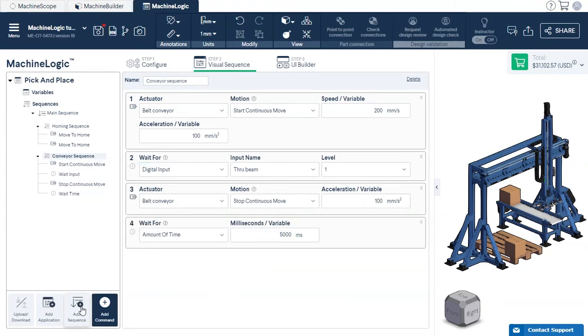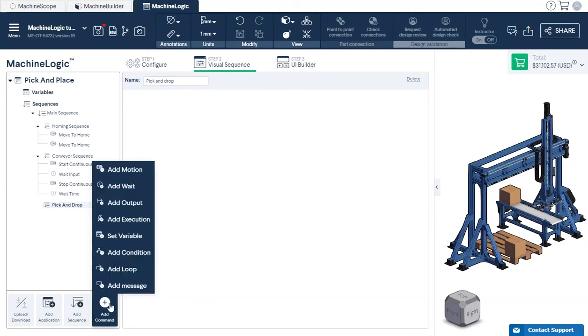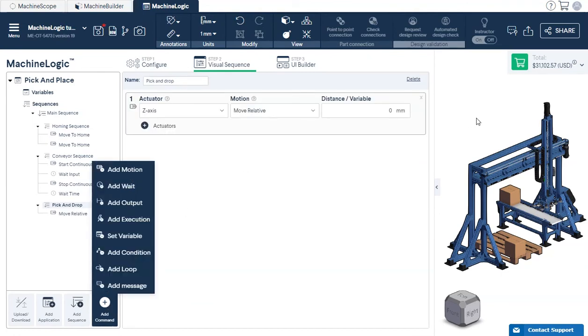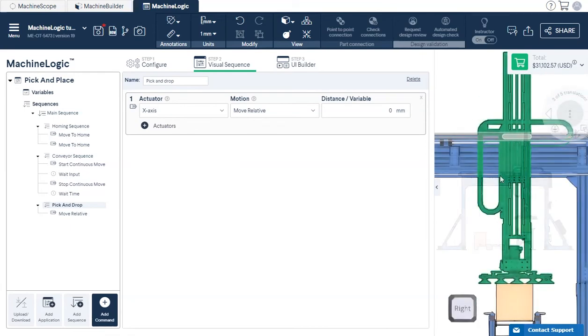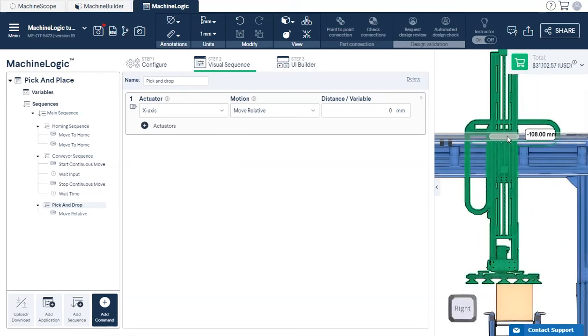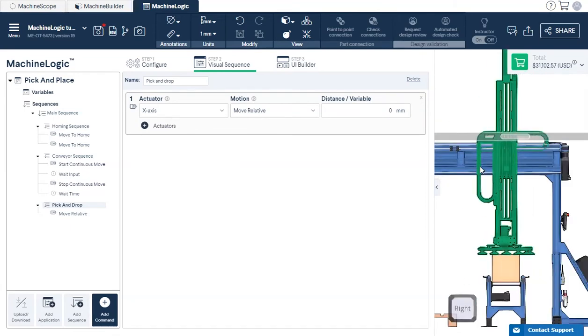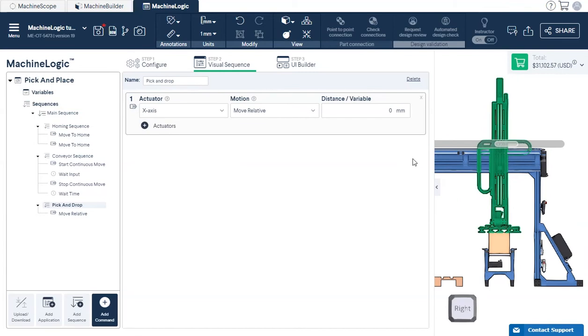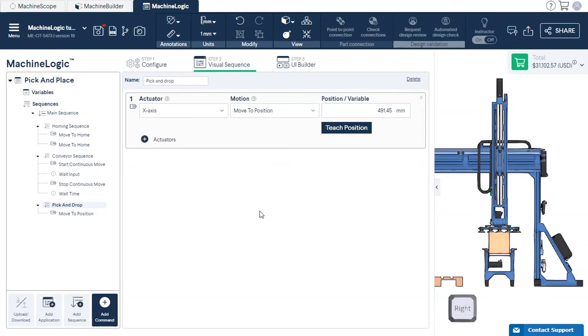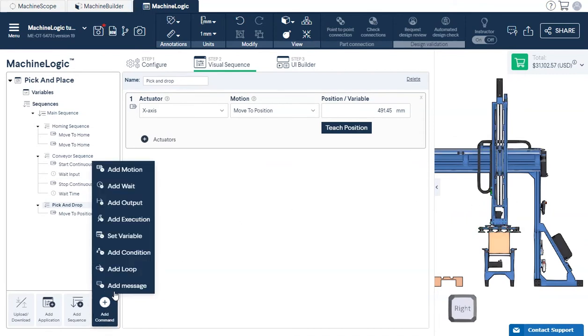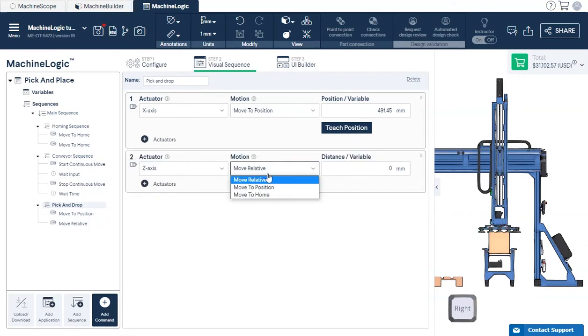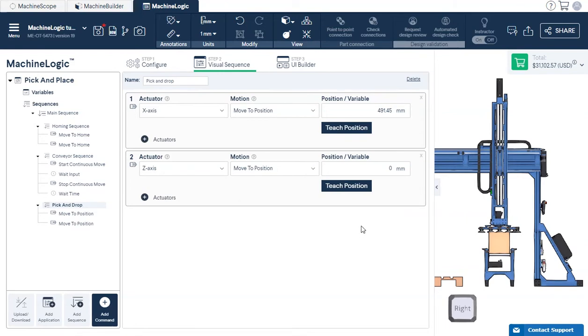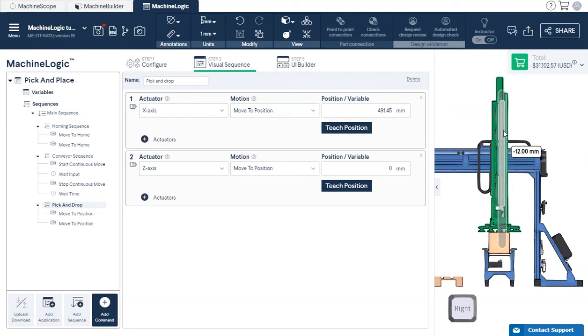For the pick and drop sequence, we'll use the Move to Position commands for our linear actuators. We can move the actuator to the position you would like to move it to, then once the desired position is reached, we'll click Teach Position to confirm. Another option would be to manually input the position value you would like. We'll speed through this and show you how the rest of the sequences are built.